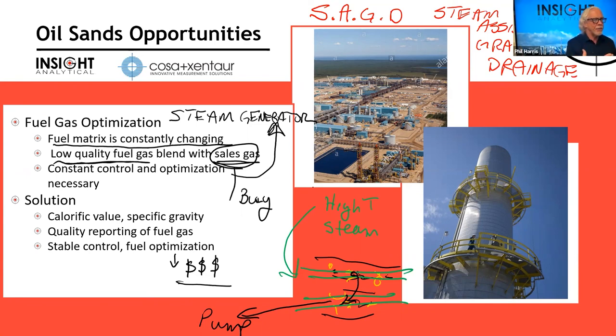If there's a small amount of water vapor in the fuel, it's not an issue. If there's liquid water there, you're going to want to knock those liquid droplets out. Hydrocarbons aren't that soluble in water, but if we let water get in, the critical orifice works perfectly for gases. If we get a drop of water come across, and then the water goes into the furnace, that small droplet of water expands to make a lot of steam, and it pushes a bunch of the other molecules out of the way. So it'll lower our overall oxygen demand when we've got liquid water that's flashing inside there.